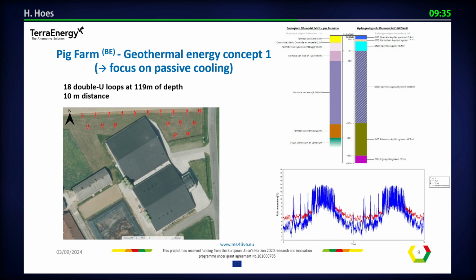Just to give you an idea, this will mean 18 double-U loops at a depth of 119 meters, given, of course, the total capacity of the heat pump in this case. Why is it 119 meters? That's a strange figure, but that's what legislation is in Belgium for a maximum depth at this point. Typically, it's 150 meters, but at this point, over this site, it's 119 meters. And in the red and blue graph, you see the ins and outs of the borehole heat exchangers. And on the top right, you see the geological description of the underground.